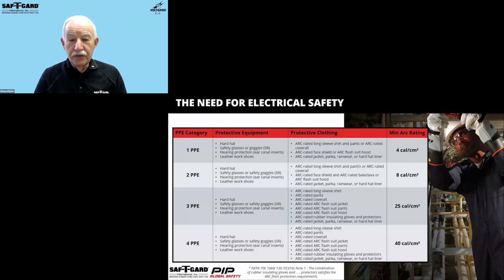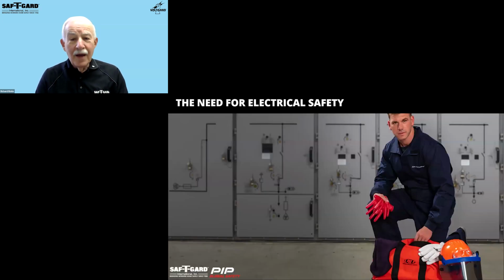The results of the analysis will usually guide the property owner regarding the controls that should be in place, engineering, mechanical, human, or otherwise, and review the hazards of both arc flash and electric shock. While there may be some isolated instances where electric shock is not present, in nearly all cases, if there's an arc flash hazard, there's an electric shock hazard because that's what's creating the arc flash. And once that analysis has been gone through, the proper PPE can be determined. One topic that's often not discussed in detail is, as I explained, the need for rubber insulating gloves where that shock hazard exists from exposure to energized equipment.